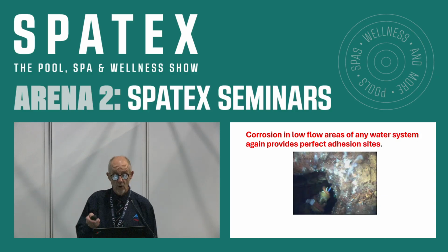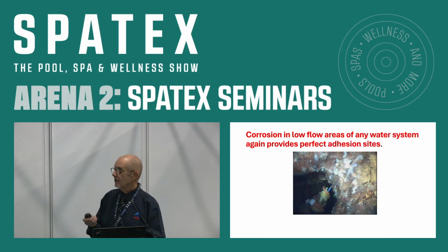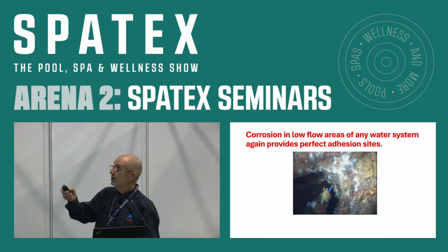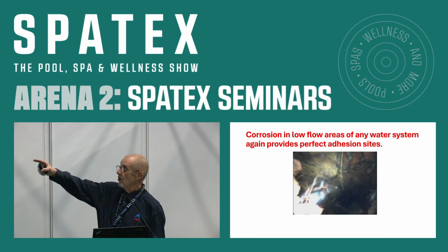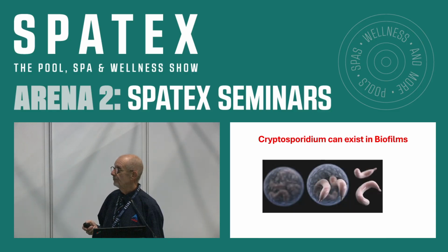Corrosion in slow-flow areas of any water system provides perfect adhesion sites. I had a 20-meter camera go down a pipe, and this was in a slow-flowing part of a system. They needed complete refurbishment. So corrosion is an ideal site. And you can see here as the camera's going down, all this stuff is in this pipework. It really should have been redundant a long time ago. You can see all the deposits in there, and amongst that is probably a biofilm.